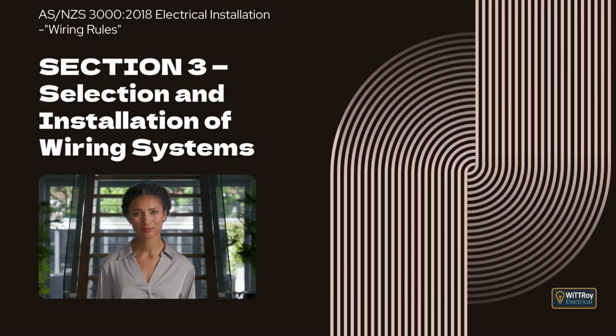When determining the required capacity, allowance must be made for changes that can reasonably be expected to occur over time, such as changes to the environment around the wiring. One specific example is domestic installations, where wiring systems must be installed on the assumption that thermal insulation may be added later in ceilings, walls, or under floors, even if it is not present at the time of installation.